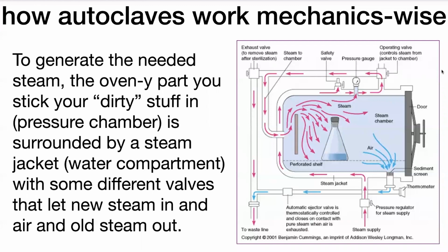And importantly, as we'll get into, we're actually pumping the steam into the chamber. So that steam that we're getting, it's not from our stuff evaporating off. Instead, it's from the steam that we're pumping in. This way, we're able to introduce this really, really hot steam without being at temperatures in the environment inside of the chamber that are actually going to cause our liquids to just boil off. We're putting this really hot steam in there. The steam is going to meet the surfaces of our containers and things, which are going to be cooler. And then it's going to transfer the heat, as we'll see, and cause the denaturation and all of this stuff. Without our samples just boiling, we're able to get this really, really hot stuff in there. So it's super cool. I mean, super hot.